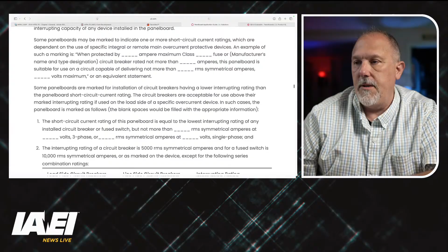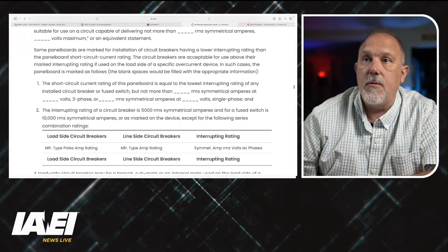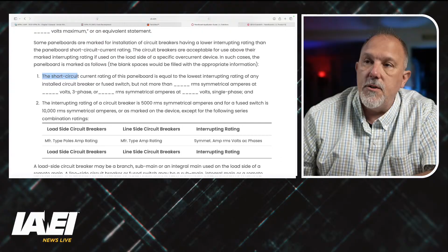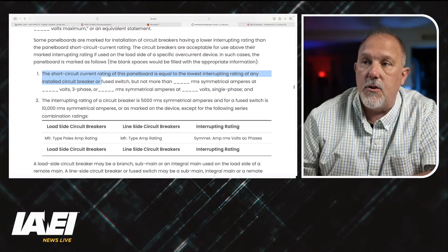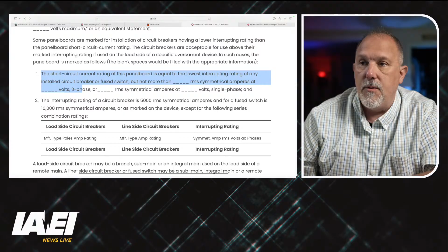So the short circuit current rating will be dependent upon the overcurrent devices that are a part of that piece of equipment. The short circuit current rating of this panel board is equal to, and I've seen this too. So remember, this is what I mean by the recipe. It says the short circuit current rating of this panel board is equal to the lowest interrupting rating of any installed breaker or fused switch, but not more than blah, blah, blah.